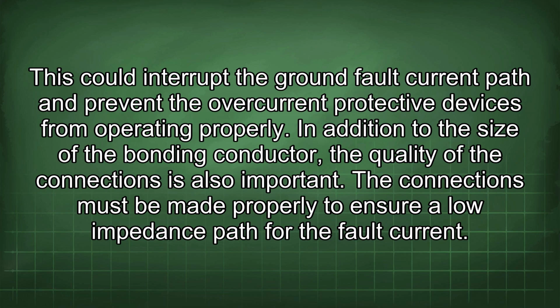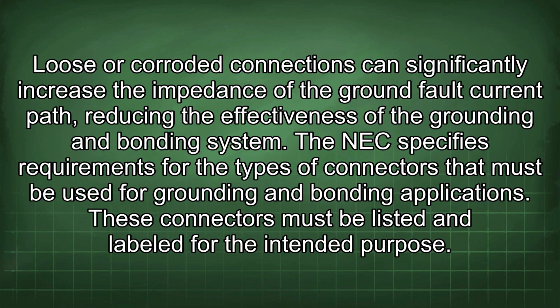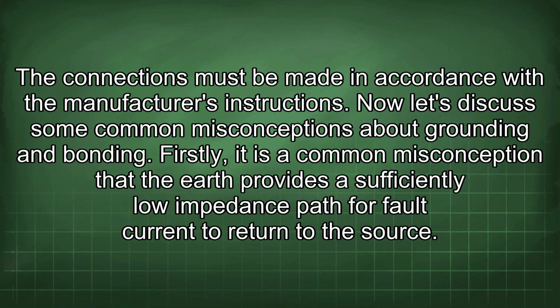In addition to the size of the bonding conductor, the quality of the connections is also important. The connections must be made properly to ensure a low impedance path for the fault current. Loose or corroded connections can significantly increase the impedance of the ground fault current path, reducing the effectiveness of the grounding and bonding system. The NEC specifies requirements for the types of connectors that must be used for grounding and bonding applications. These connectors must be listed and labeled for the intended purpose. The connections must be made in accordance with the manufacturer's instructions.